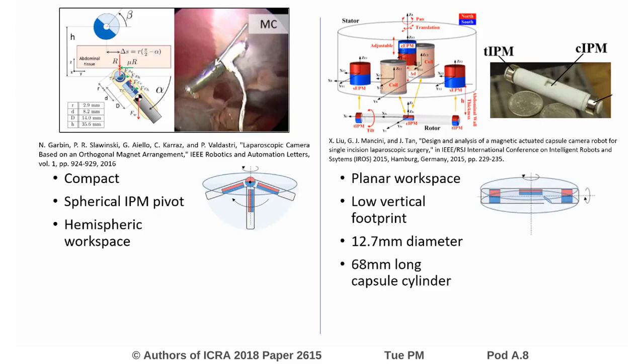Typically, magnetic-anchored cameras either do not allow tilting or rely on onboard motors for actuation, which adds to the device's bulk and weight. Two notable exceptions are the magnetically-actuated cameras developed by Nicolo Garbin and Xiaolong Liu. One uses a spherical magnet as a pivot and has a hemispheric workspace. The other uses electromagnetic drivers to steer the capsule camera, which is 12mm in diameter and 68mm long.